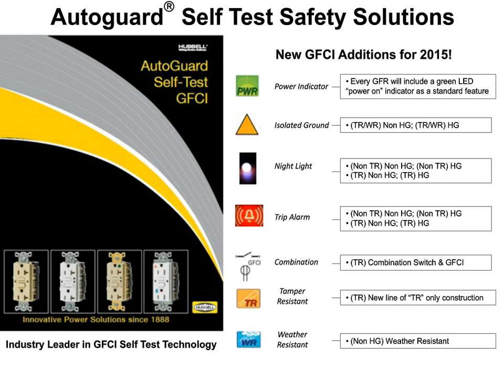We had a lot of college campus facilities with labs where they wanted isolated ground in addition to ground fault. So that's now available with this new UL standard. You now have a nightlight version. We see a lot of hotels and residential applications where they want nightlights built in. Some people want an audible alarm.